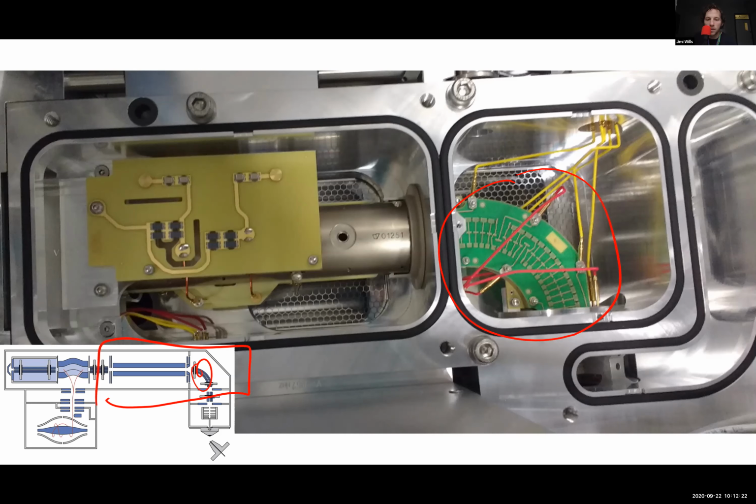The point of it is, I guess there are 2 points. One is to control the form factor of the instrument. So if you can redirect the ions in a different direction, you can squeeze your components into a smaller bench space. But also anything that's not charged will now just hit the back wall, which means you're not filling any further into the instrument with stuff that you can't manipulate. I guess that's kind of important, because the next part is quite difficult to take out and clean.